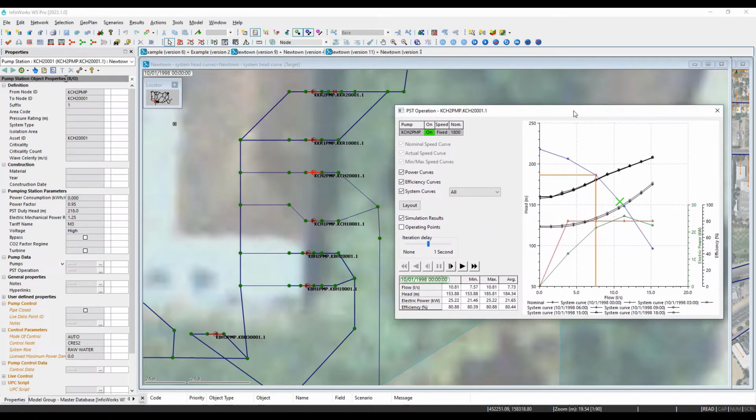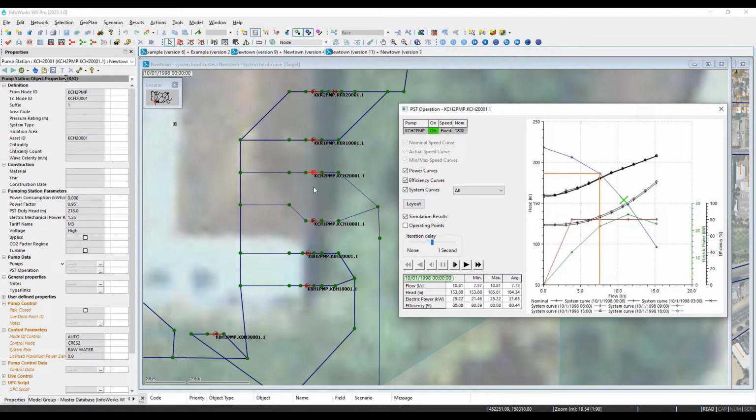In configurations like this, where pumps are sometimes operating in parallel and sometimes individually, you may notice separate clusters of system curves. In this case, the lower set of curves occur as the pump is operating by itself, and then when both pumps are competing with each other, adding downstream head, that will raise up the static head required to deliver flow, and you'll have this upper flow curve.